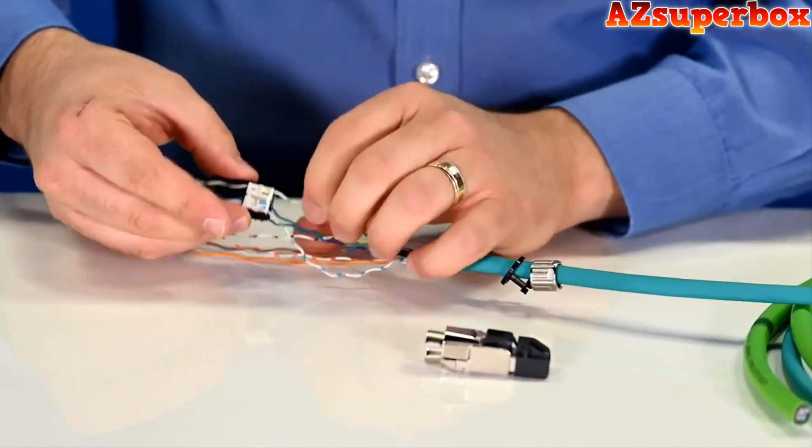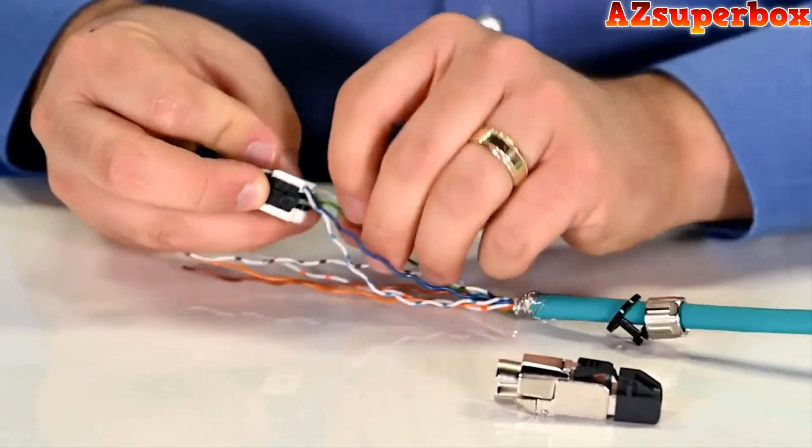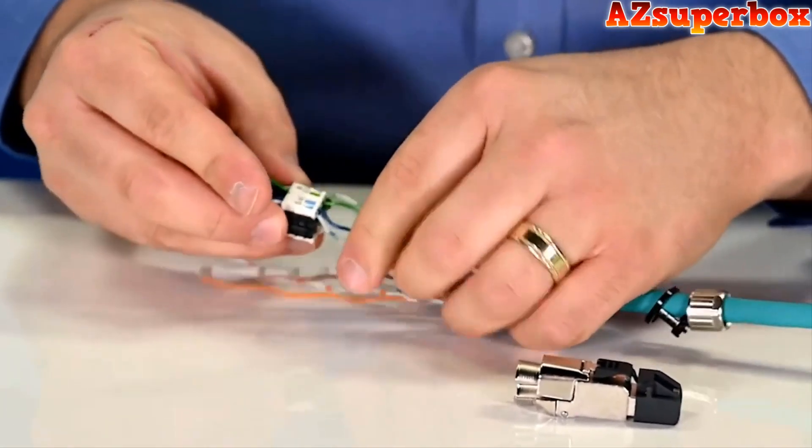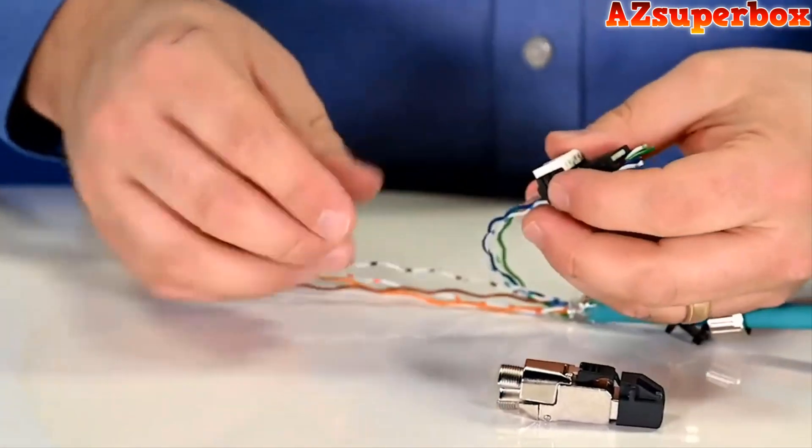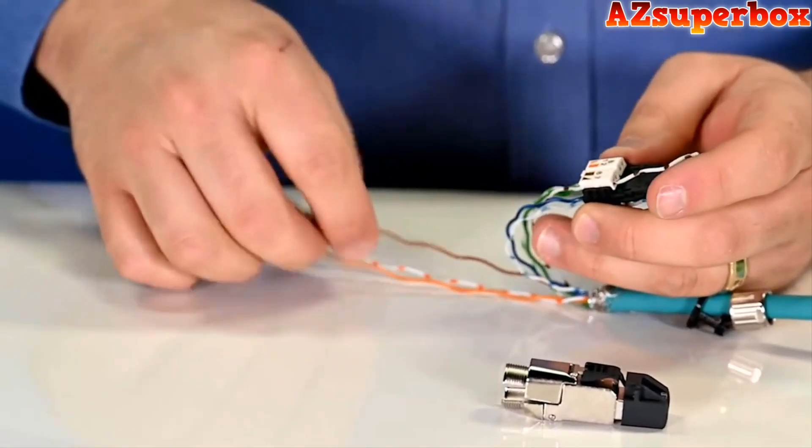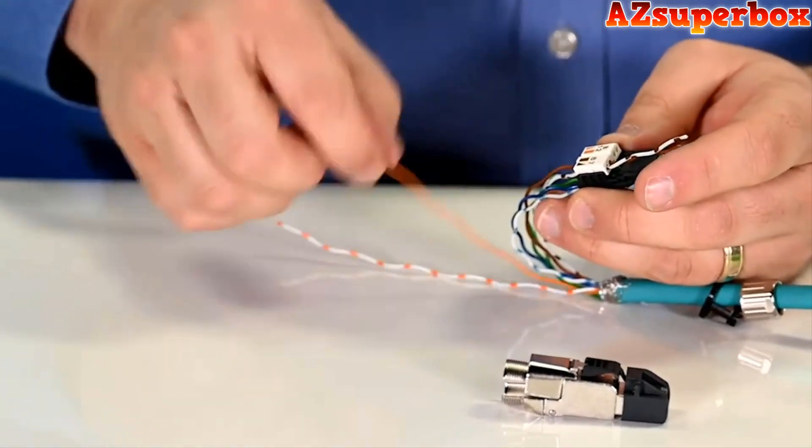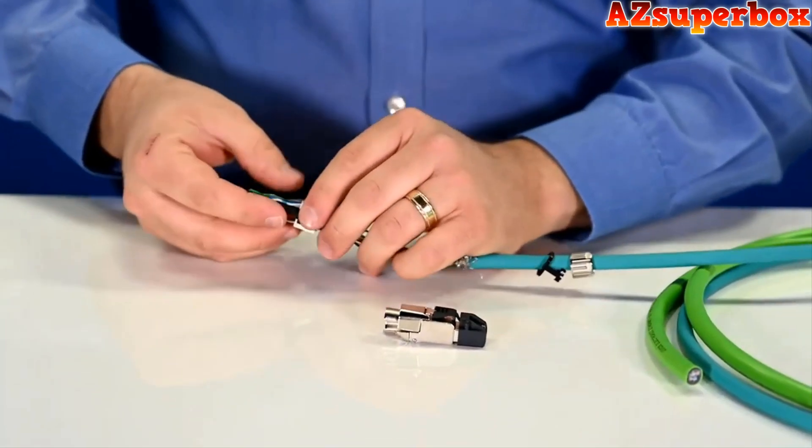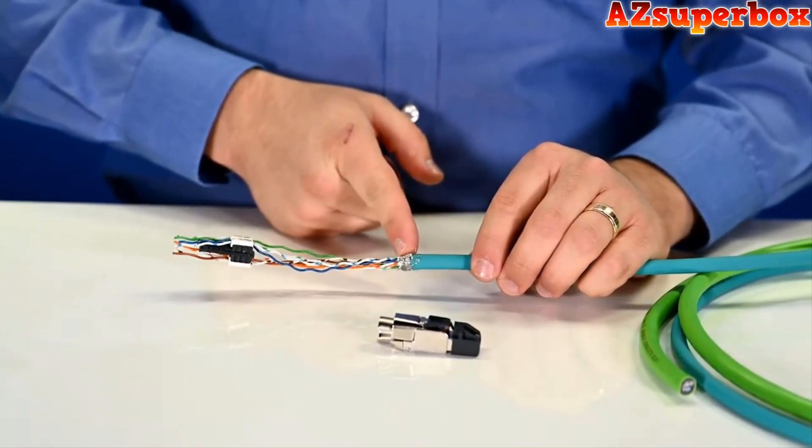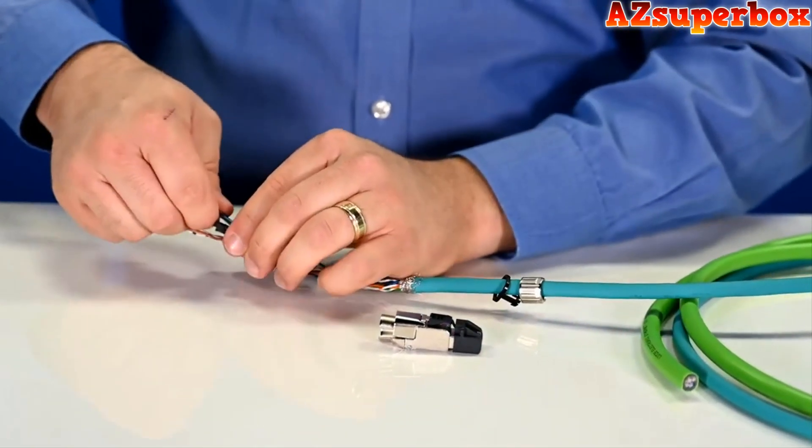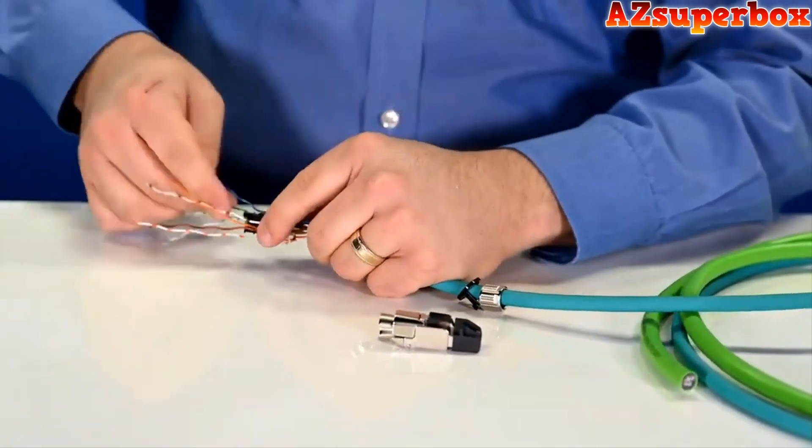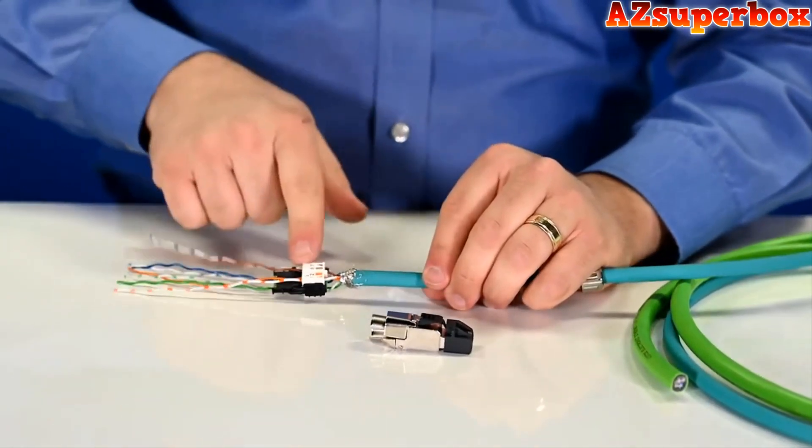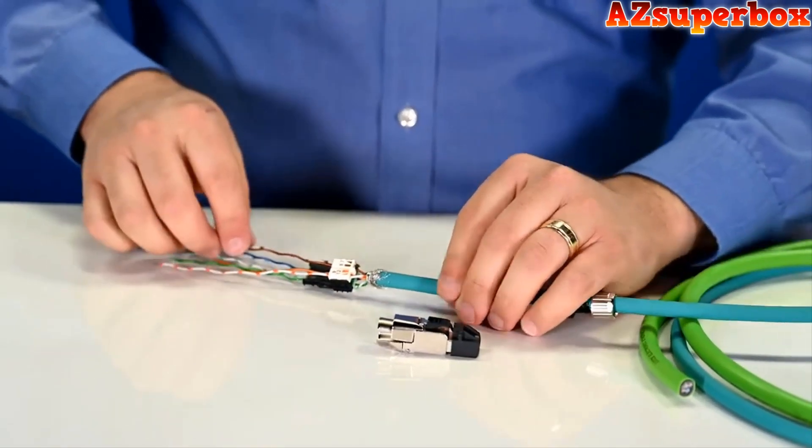So we just simply match each conductor with the corresponding color on the connector. And you'll see those conductors are going all the way through the connector housing. Do the same thing on the back side. And now all we have to do is slide this part of the connector all the way down against our cable jacket. We want to make sure that connector is nice and tight against the cable to eliminate as much of this unshielded area as we can.